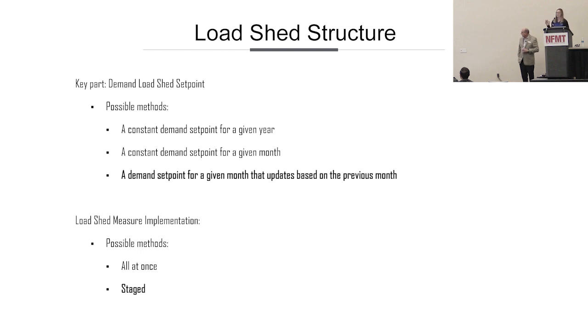And so I've got a coworker that helped me on this project too, and he was some of the brains behind the model for it. And it's a big math slide that I did not include on purpose on this one. But basically, every month it looks at the previous month and alters that set point to reflect what it's probably going to expect. And it does that on a yearly basis. And so it's constantly changing, constantly learning, okay, this is about what the load was for this month. And so that was the set point brains behind it, instead of changing the set point manually or having a constant set point throughout the year, because it is Alabama. We have those cold months, we have those hot months, so it does not really make sense to do one set point all year long.